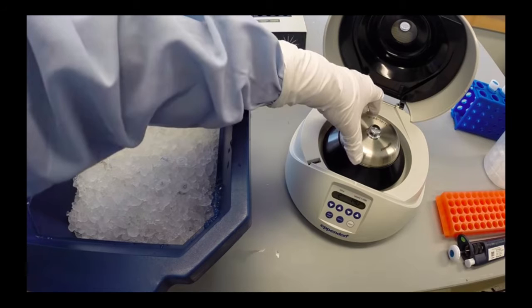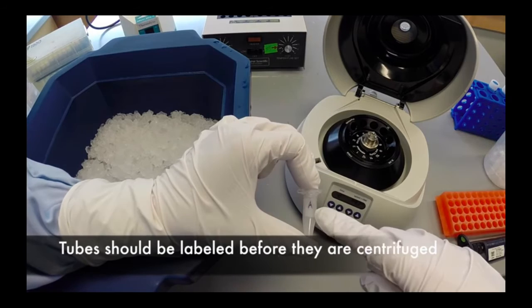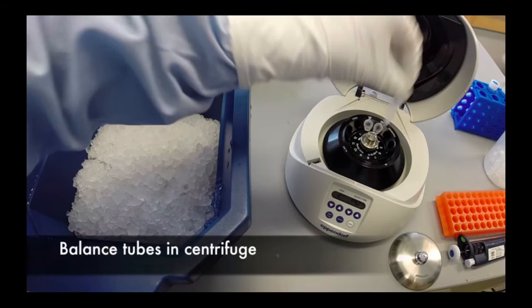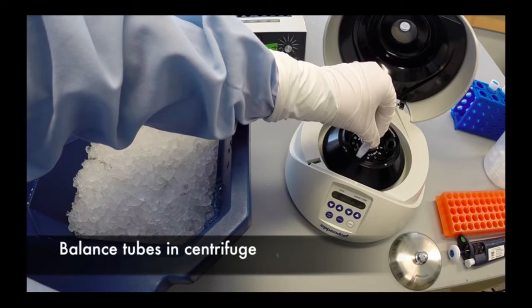Make sure that the tubes are labeled either with letters or numbers before loading them into the centrifuge. Load samples with hinges facing outward, and balance the tubes across the rotor by ensuring that all tubes have equal volumes. Replace the metal lid and press it until it clicks securely onto the rotor. Close the lid to the microcentrifuge gently.